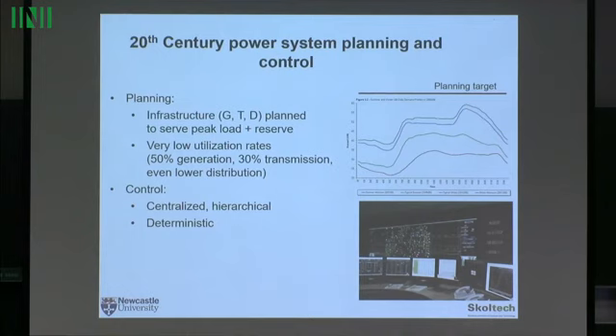It's deterministic, because everything was highly predictable, and preventive, based on N-1 reliability criteria, which I'll talk about a lot - meaning the system has to be secure not only under what is assumed to be normal operation, but also when one single element fails, a so-called credible contingency. Because it has to be safe as well, since anything may happen at any time, lightning may strike, whatever - we still have to survive.